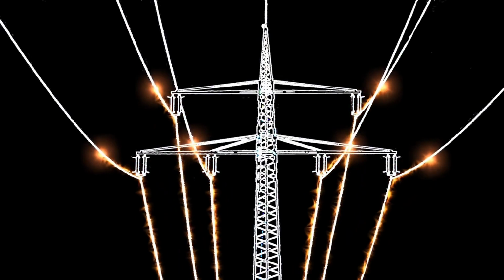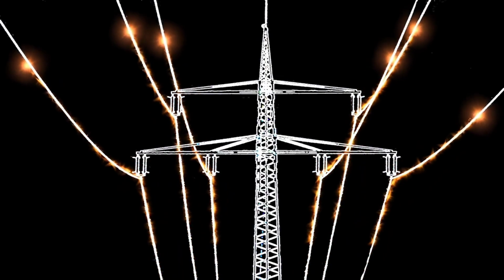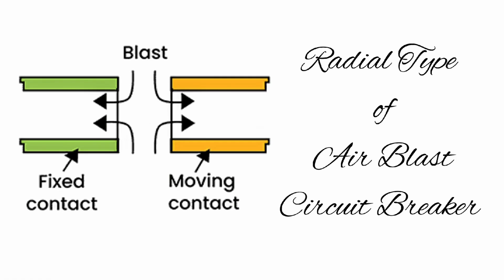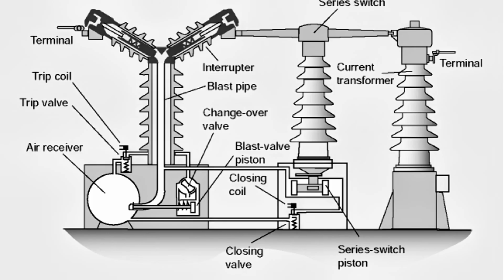The last type of air blast circuit breaker we will analyze today is radial blast type. The radial blast type of air blast circuit breaker, ABCB, is designed where the air blast is directed radially outward from the center of the arc. When the contacts of the circuit breaker open during fault clearance, an arc is formed between the contacts, and compressed air is blown radially outward, effectively cooling and extinguishing the arc.